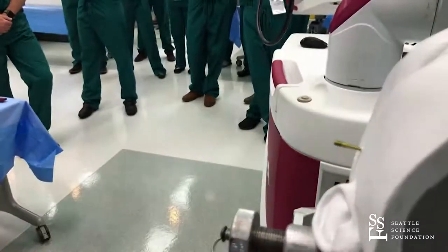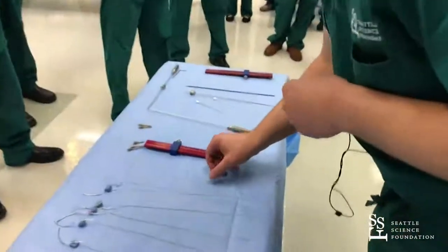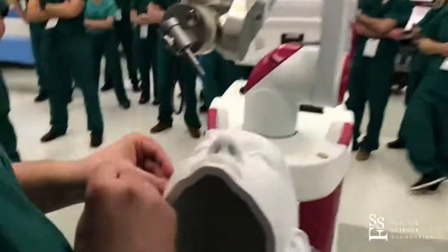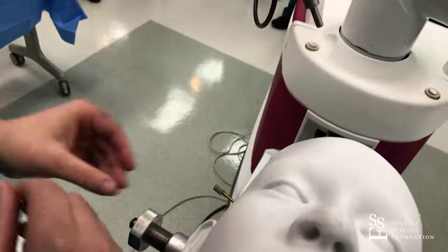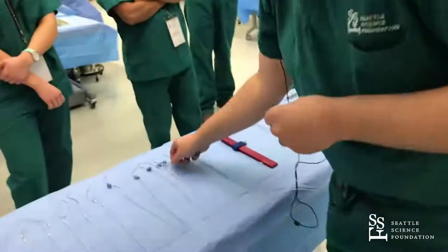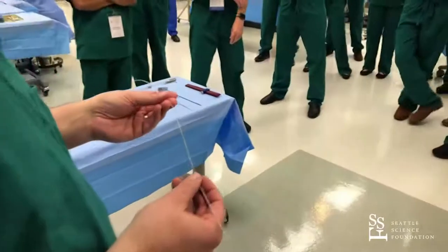Great. We've measured our lead. And do we have the cap? Great. Some people put the cap on the actual lead. We put the cap on first and add another 4 millimeters. I like it the way we do it. Great, so that's loose. And then we get our lead. What was our depth to target? 73. So if it's 73, we would ask for a 6.